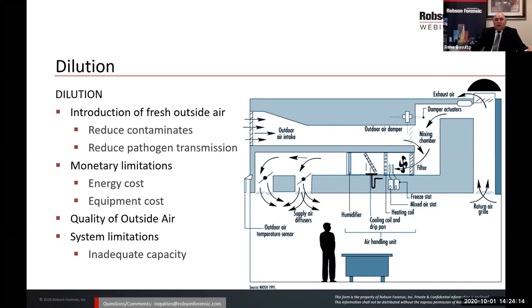There are industrial and pharmaceutical production facilities where we bring in 100% outdoor air because you don't want to have that contamination. There are other facilities. We just finished designing a quarantine intake facility for the Greater Miami Humane Society where we're bringing in 100% outdoor air, not so much to prevent transmission, but to control the odors inside the space. You don't want to be recirculating that air.